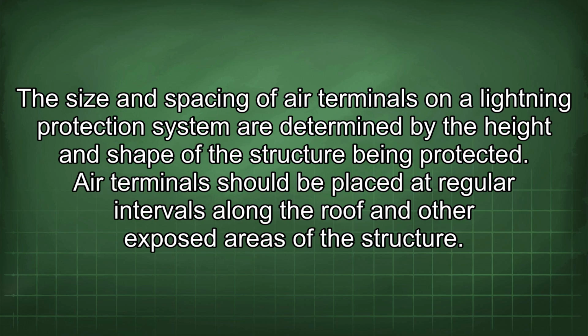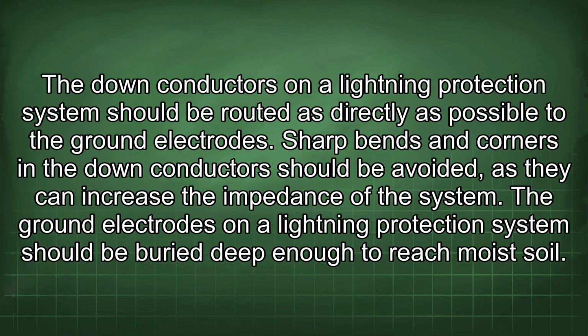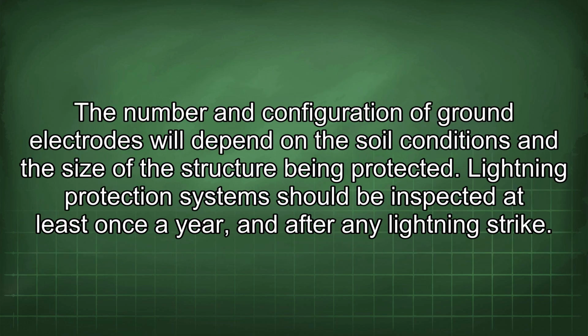The down conductors on a lightning protection system should be routed as directly as possible to the ground electrodes. Sharp bends and corners in the down conductors should be avoided, as they can increase the impedance of the system. The ground electrodes on a lightning protection system should be buried deep enough to reach moist soil. The number and configuration of ground electrodes will depend on the soil conditions and the size of the structure being protected.